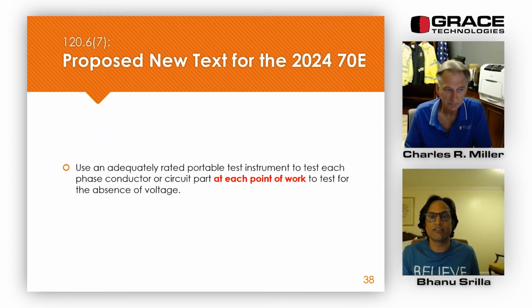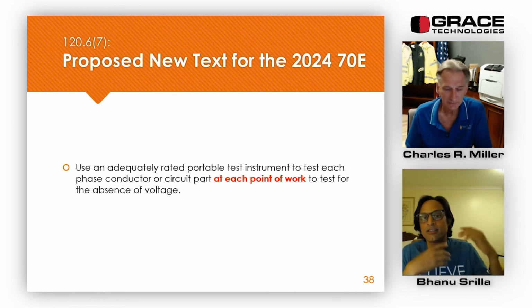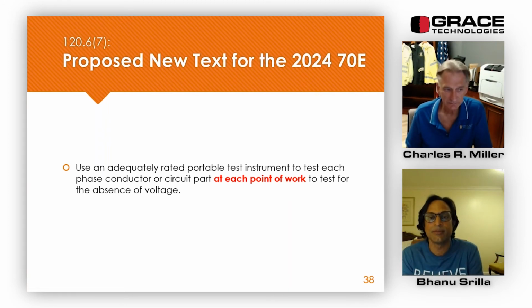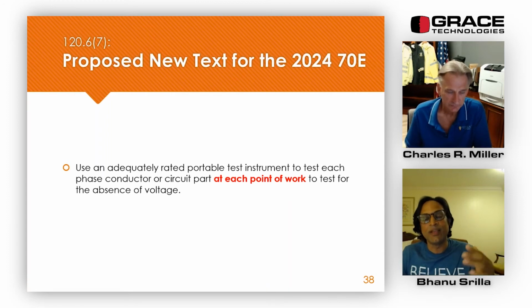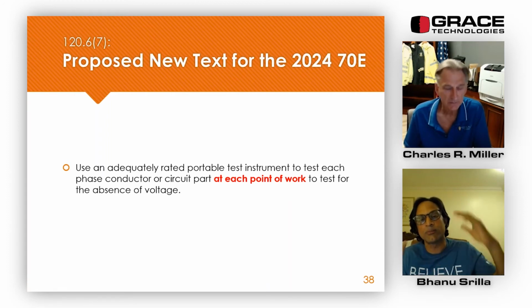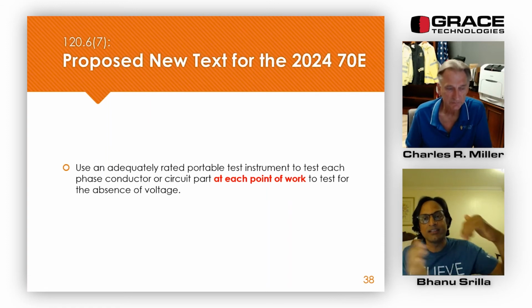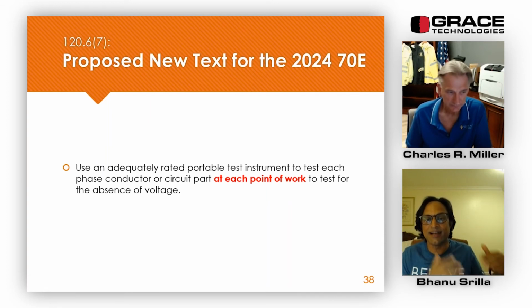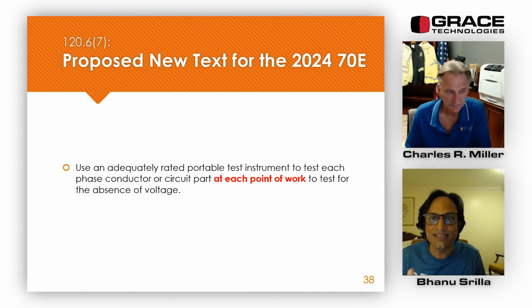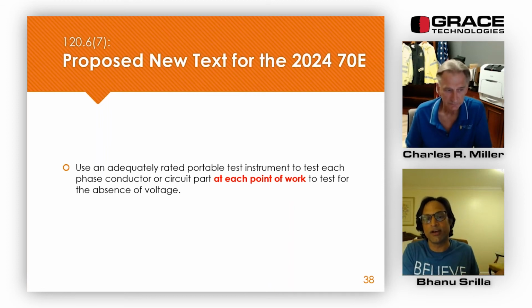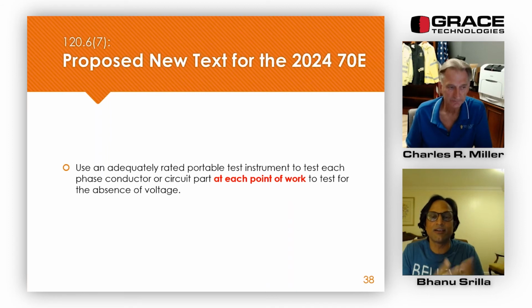But what this language tells you is, for the same panel, if you have a contactor or a thermal relay or any other component built in, you need to go and verify voltage at each point of work. That's going to be very cumbersome and very time consuming, and it doesn't make sense. Even if you have a panel that has two feeders incoming, as long as you verify that the two feeders feeding this panel are shut down and both are locked out, everything downstream has been completely isolated, verified, and put in an electrically safe work condition. There is no need for verifying at each point of work, right? So that's where we're going with that.